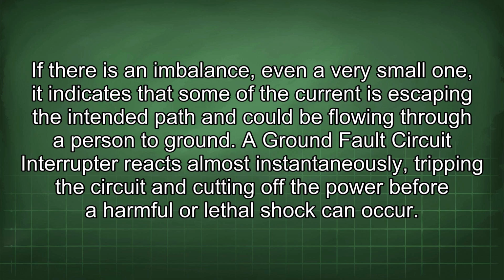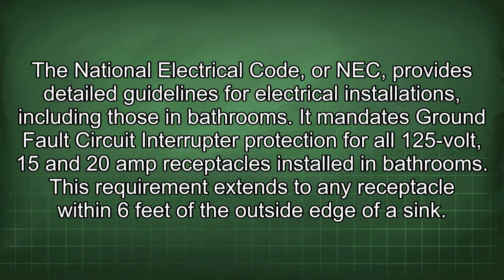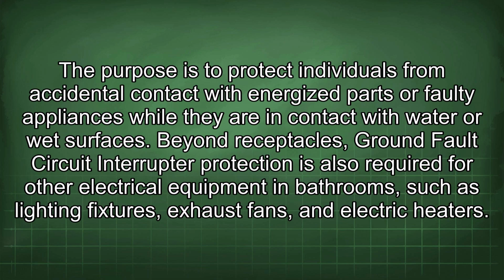lethal shock can occur. The National Electrical Code, or NEC, provides detailed guidelines for electrical installations, including those in bathrooms. It mandates ground fault circuit interrupter protection for all 125-volt, 15 and 20-amp receptacles installed in bathrooms. This requirement extends to any receptacle within 6 feet of the outside edge of a sink. The purpose is to protect individuals from accidental contact with energized parts or faulty appliances while they are in contact with water or wet surfaces.